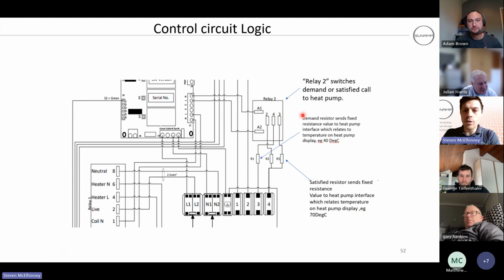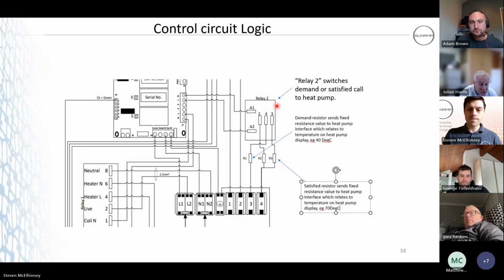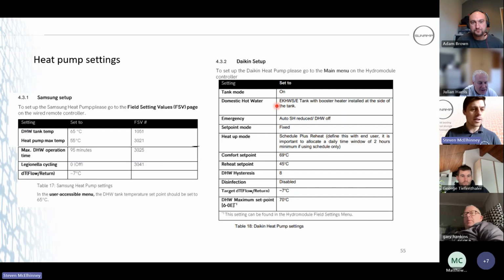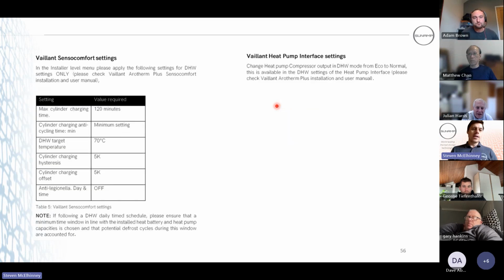So that, yeah, this control circuit logic. So relay 2 switches demand or satisfy call to heat pump. So the demand resistors send a fixed resistance value to the heat pump interface, which relates to the temperature on the heat pump display. For example, when there's a demand, it'll be 40 degrees. The satisfied resistor will send a fixed resistance as well, which will equate to about 70. So you only get the two. So it's basically, think of that like a cylinder stat, like off and on. You know, this is just straight from the manual. You've got your heat pump settings there. So just reference that when you're working on it.